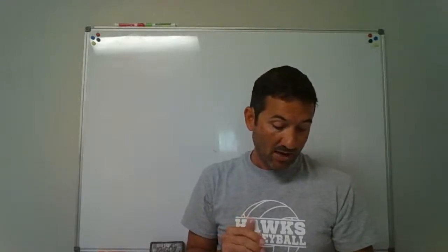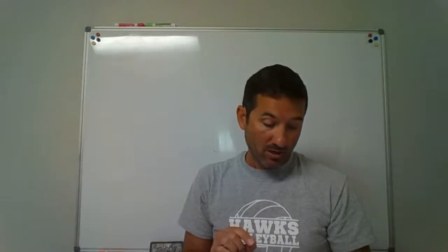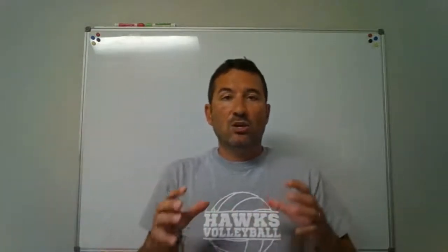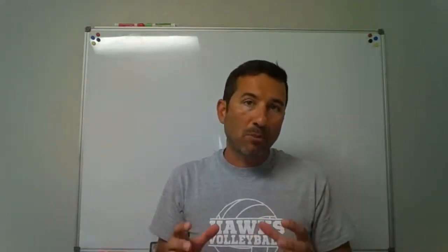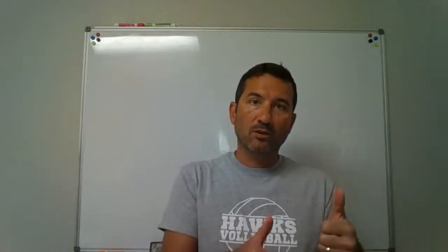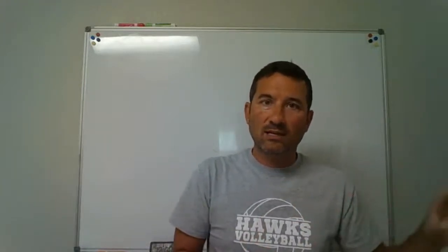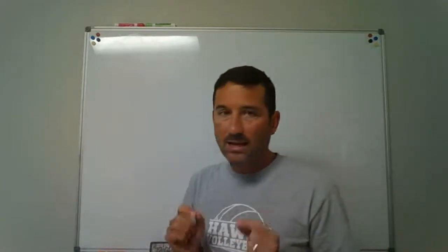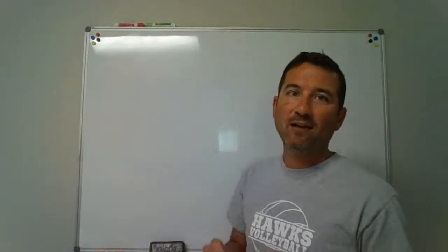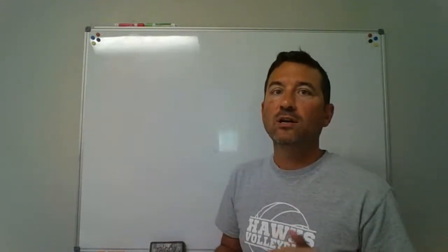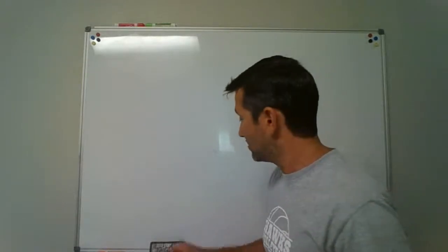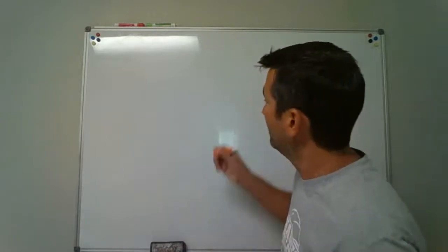Let's jump down to 712 on sumps and ejectors. Okay, so a sump or ejector is used if you might need some type of pump to pump the liquid, the drainage, the sewage and everything else up to where it can end up flowing by gravity. Any part of the plumbing system that does not flow by gravity is called that building's sub drain. Okay, so it's lower than the point where it's going to flow out by gravity.